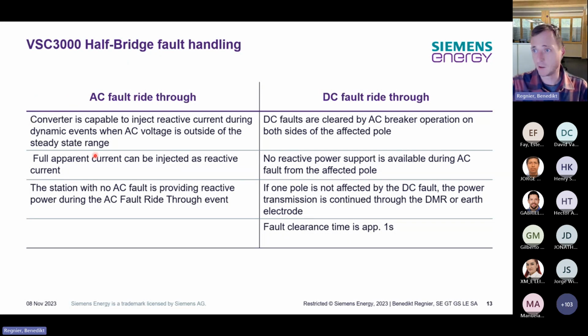On the AC side, during AC events the converter is capable of injecting reactive current as needed to support the AC fault and to make sure that the grid remains as stable as possible. And for DC fault ride-through, DC faults we need to clear with the AC breaker. In the majority of the projects, it's anyway a cable that we see. And if there's a failure on the DC cable, we need to open the breakers, and it is not possible to re-energize again. Nevertheless, it could also be an overhead line connection. Then we have fault clearance times of roughly 1 second.